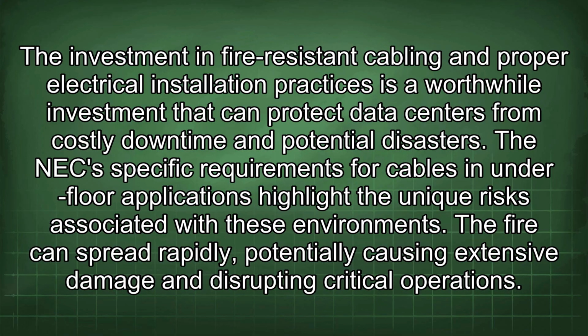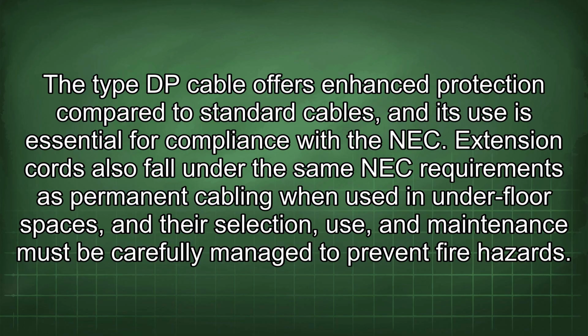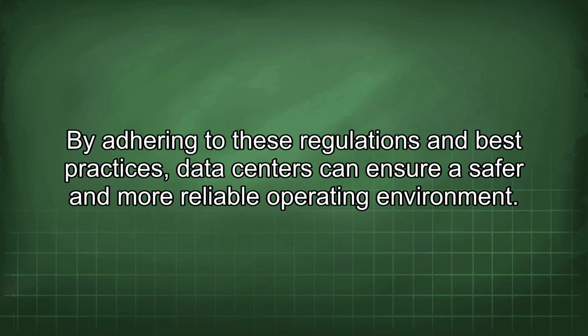The NEC-specific requirements for cables in underfloor applications highlight the unique risks associated with these environments. The fire can spread rapidly, potentially causing extensive damage and disrupting critical operations. The Type DP cable offers enhanced protection compared to standard cables, and its use is essential for compliance with the NEC. Extension cords also fall under the same NEC requirements as permanent cabling when used in underfloor spaces, and their selection, use, and maintenance must be carefully managed to prevent fire hazards. By adhering to these regulations and best practices, data centers can ensure a safer and more reliable operating environment.